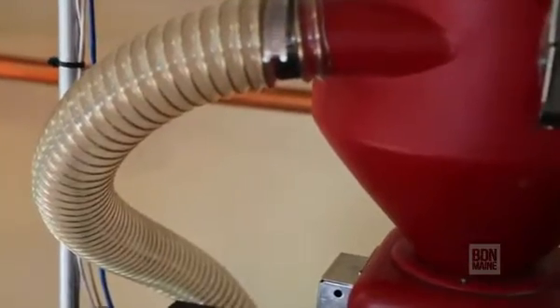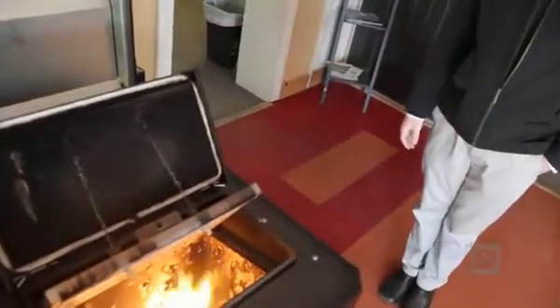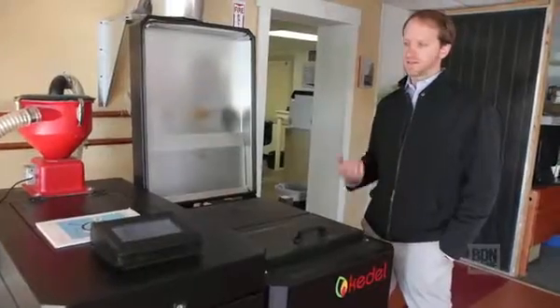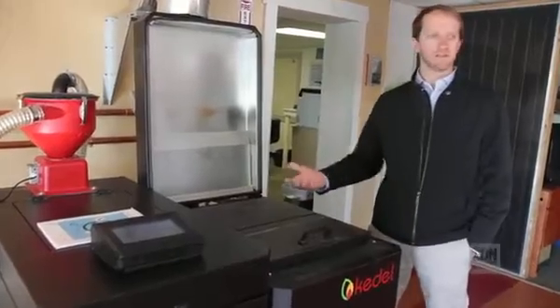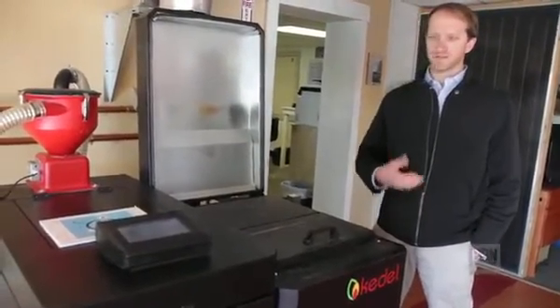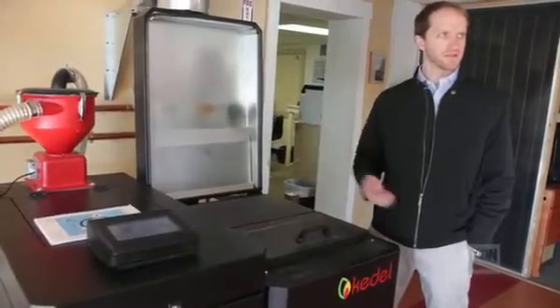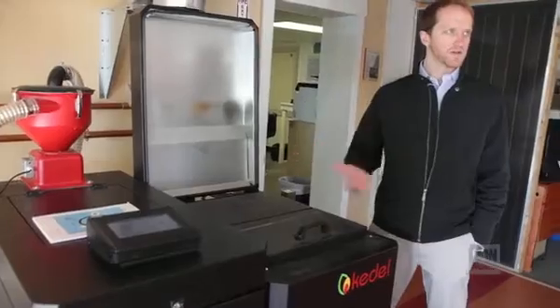The temperature and the output of the boiler is managed by the outdoor weather compensation. So it knows what the temperature is outside and what the weather conditions are, factors in the wind chill, and takes everything into account to determine how much heat the building is going to need. That way it has nice long continuous slow heat running cycles and provides heat over long periods of time, keeping the space at a very constant temperature.